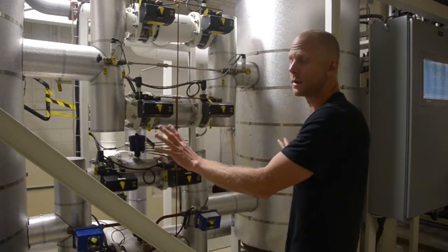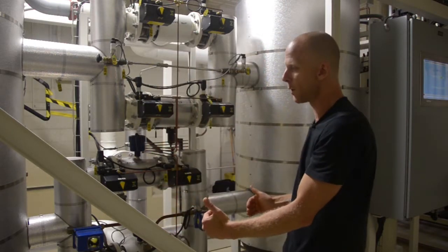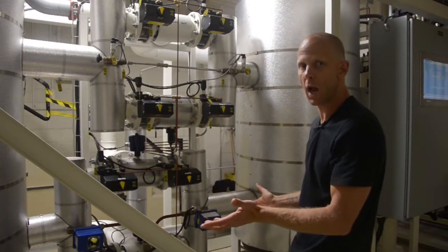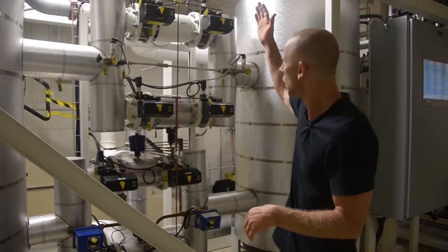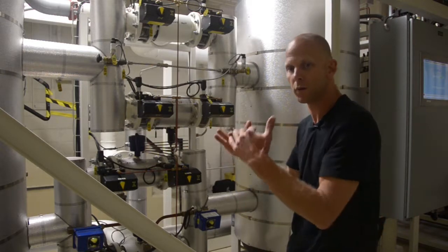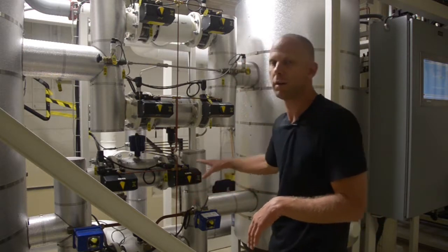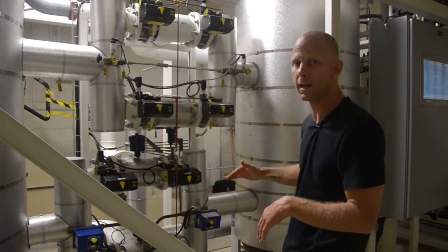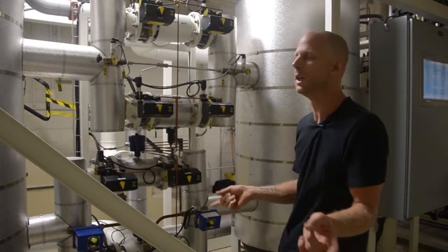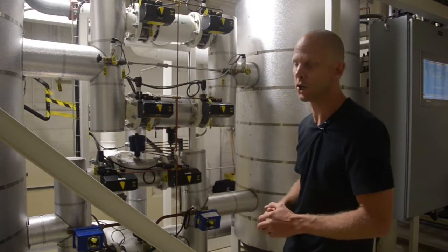So then you will have two beds online in parallel, both with their main online valves open. There's a parallel period of about 30 minutes in which both beds are used online. After that, the PLC will close the previously online bed and depressurize it. Once it's reached a certain depressurization set point, it will then open our regen valves for that bed, and that bed will become the regen bed. And so we have an 8-hour cycle in which the beds swap between regen and online functions.